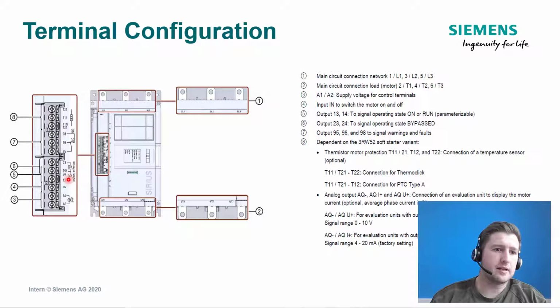There's another signaling contact here. This is mainly for the arrangement of the device. So 13, 14 and 23, 24, they're signaling contacts. So when you initiate a start, the device will enter the on mode, and so this can provide a signal to the user to tell you that an external signal that the device has been switched on.